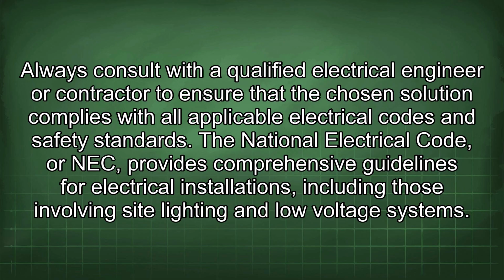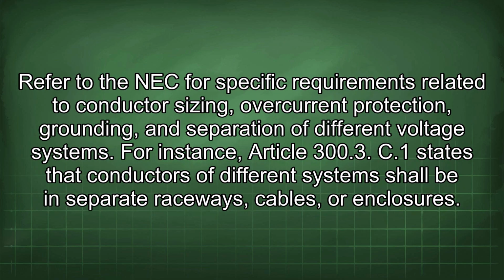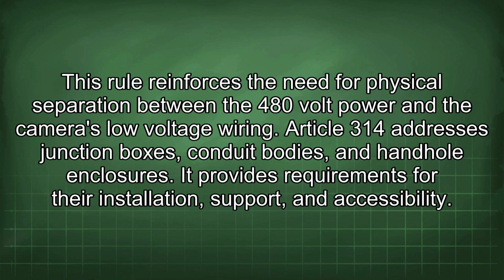Always consult with a qualified electrical engineer or contractor to ensure that the chosen solution complies with all applicable electrical codes and safety standards. The National Electrical Code, or NEC, provides comprehensive guidelines for electrical installations, including those involving site lighting and low-voltage systems. Refer to the NEC for specific requirements related to conductor sizing, overcurrent protection, grounding, and separation of different voltage systems. For instance, Article 300.3(C)(1) states that conductors of different systems shall be in separate raceways, cables, or enclosures. This rule reinforces the need for physical separation between the 480-volt power and the camera's low-voltage wiring.